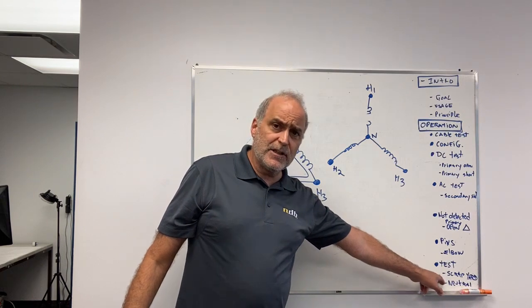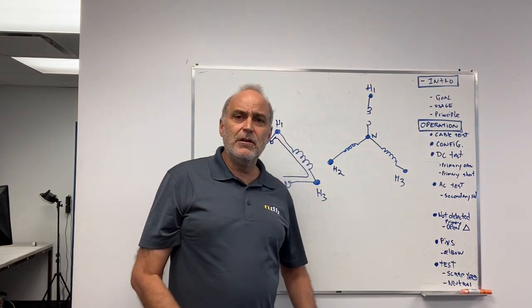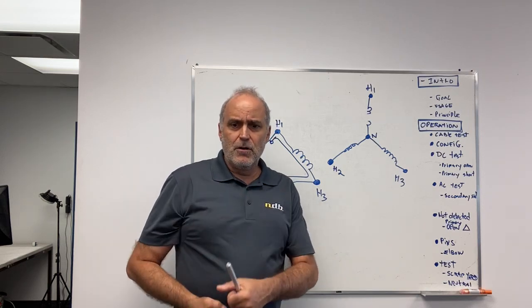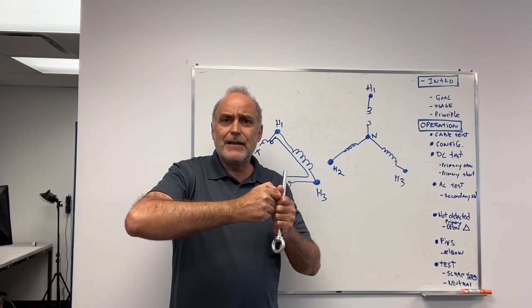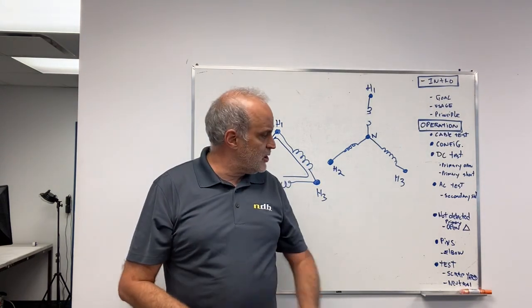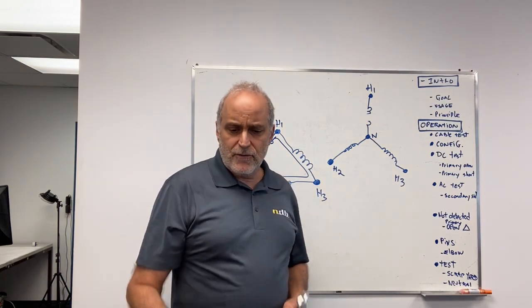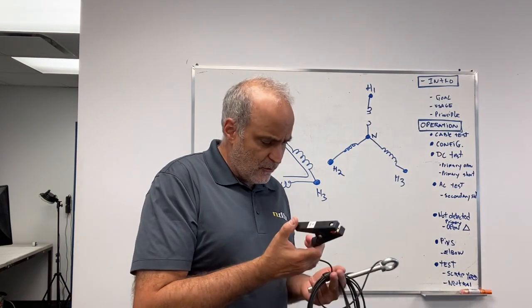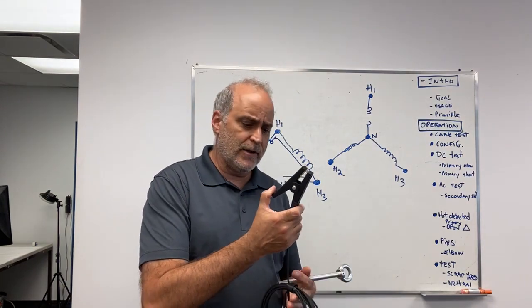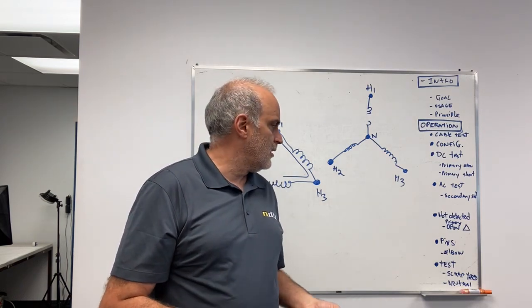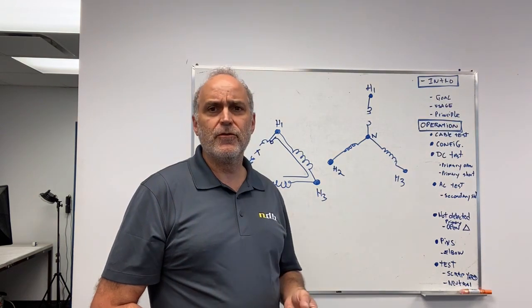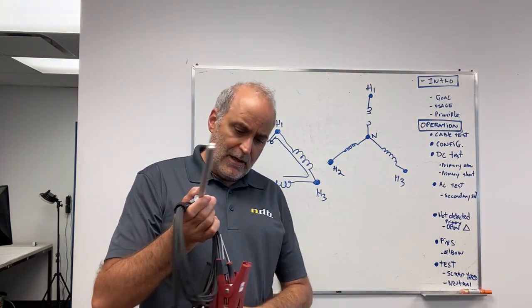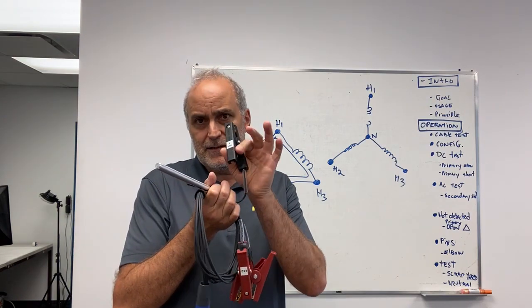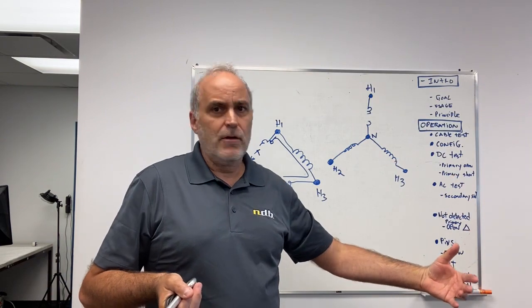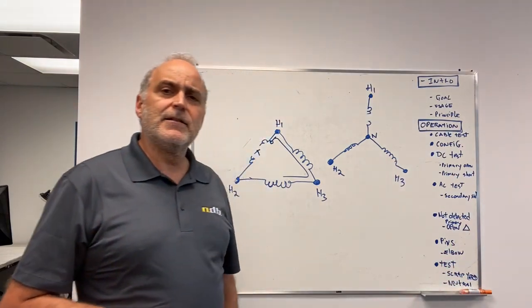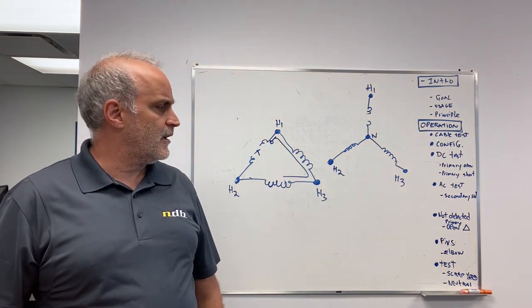One point, if you're outside, be careful about floating neutral. If the neutral is a bushing, for example, or let's say a screw, a bolt that needs to be connected to the case, make sure the neutral is connected to ground. So don't forget, on many transformers, the neutral and the case are not connected when they are new, or when they come out of the factory. So don't forget the neutral. Look for where the neutral is connected. If the neutral is not connected anywhere and you connect this clamp to the case of the transformer, they are two different points. So it will not detect any fault to the body.